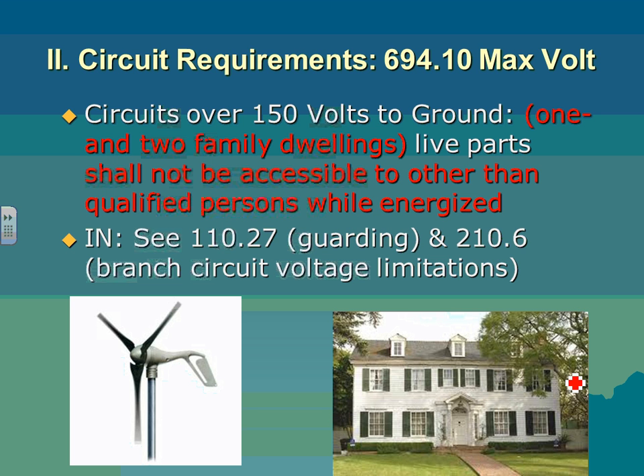then on a one- and two-family dwelling, remember that dwelling, because a lot of people are becoming environmentally friendly when they install this system in their backyard, it has to be accessible only to qualified people. All this equipment has to be accessible to qualified people. It has to be guarded, and the branch circuit also has to have some branch circuit limitation, the same thing, a limitation on the voltage that you can burn equipment at. You can see, but you don't see anything about commercial industrial.